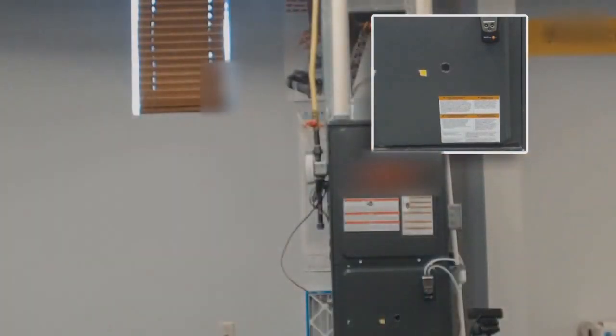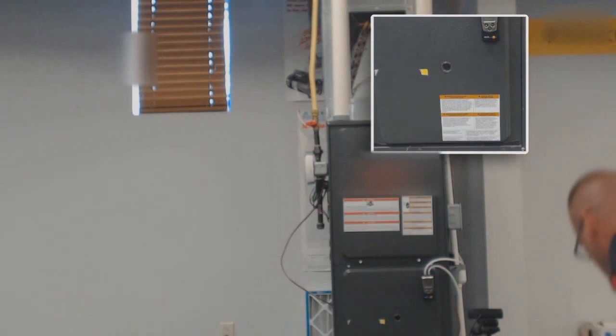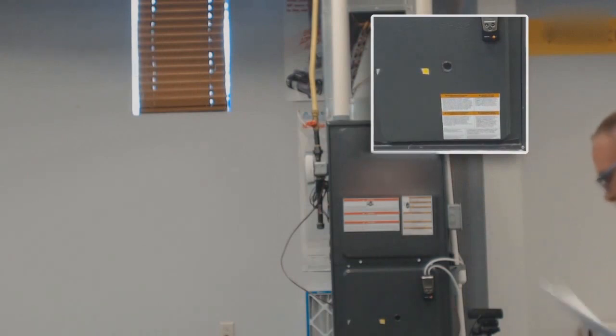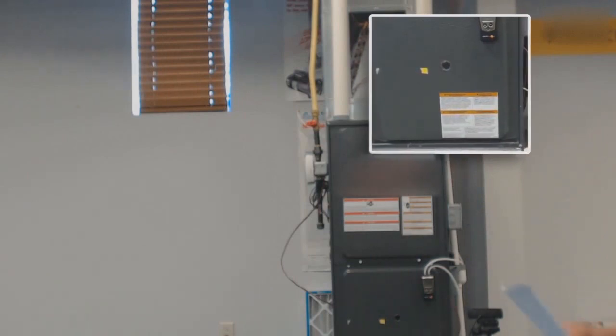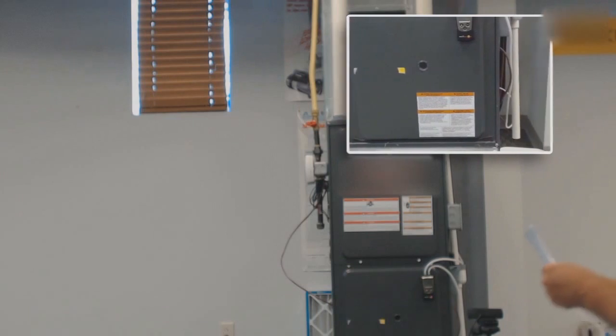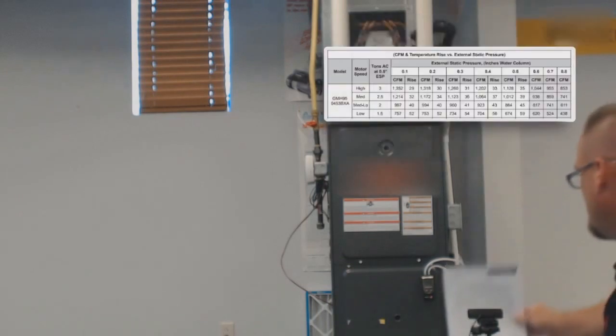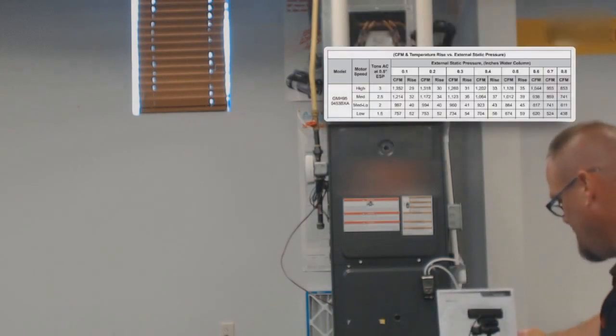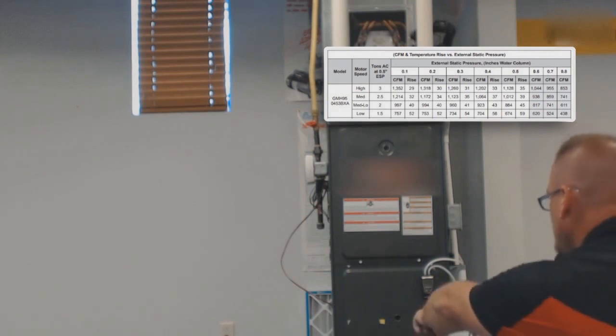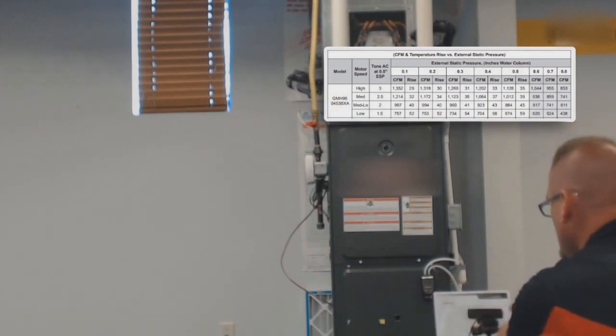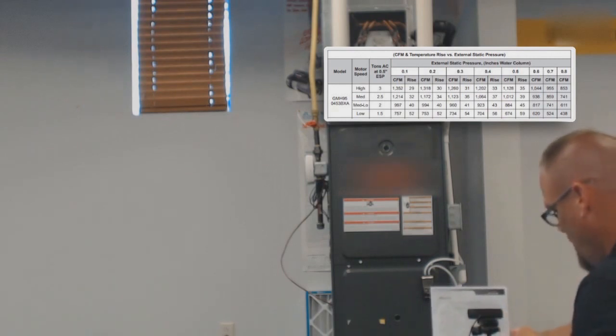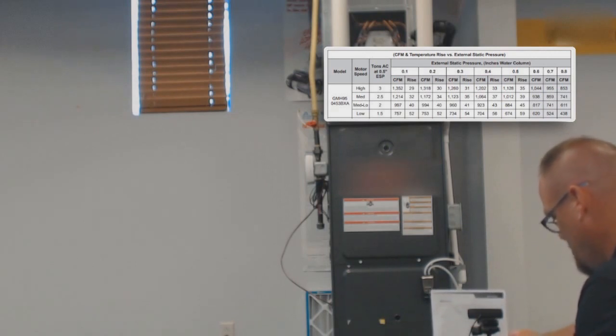What does that mean on our CFM? Because that's traditionally where the manufacturer would have left this, on high speed. That would be the manufacturer factory setting. So in looking at this, what would high speed have meant? Well, high speed at 0.6 inches of static would be 1,044 CFM. Way too much airflow for what we're looking for.